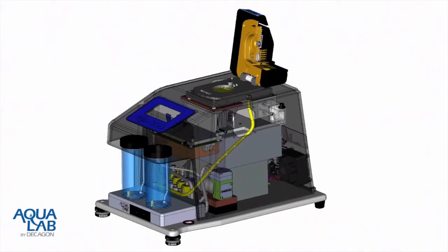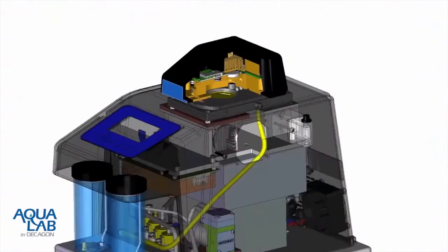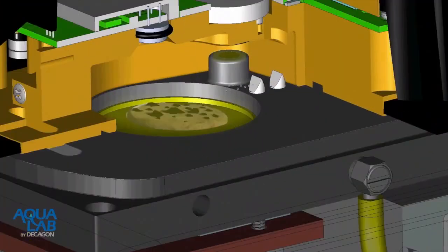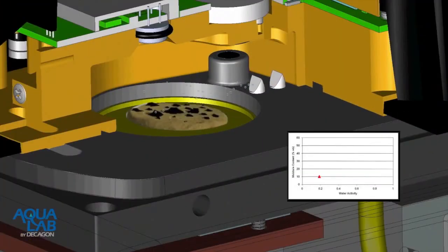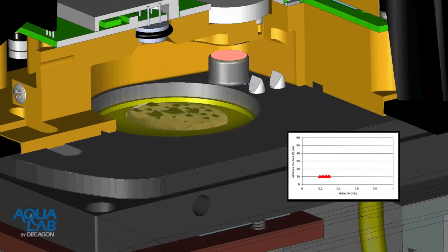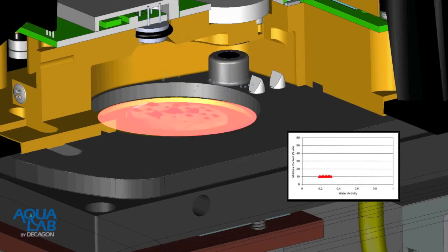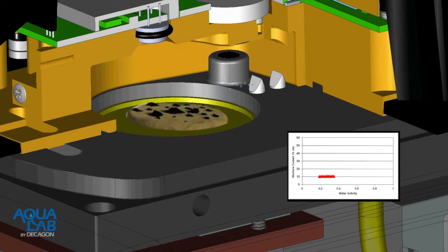For this method, instead of holding a sample at a given humidity until equilibration, the sample is exposed to saturated wet air for adsorption and desiccated dry air for desorption. As the sample dynamically takes up or loses moisture, the change in humidity is determined directly using a dew point sensor and the weight change is tracked with a precision balance.